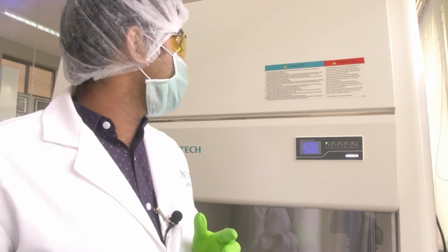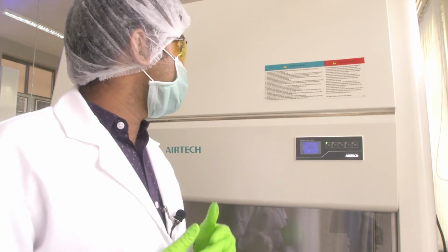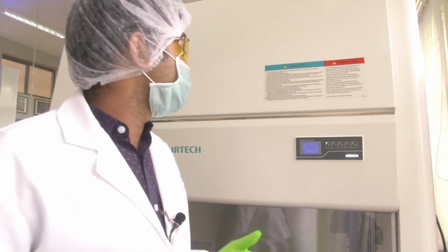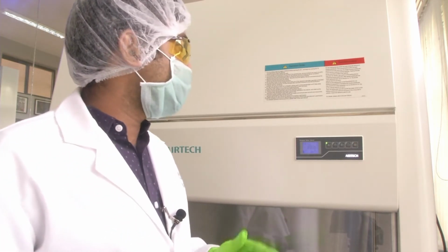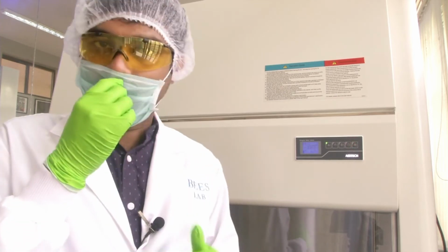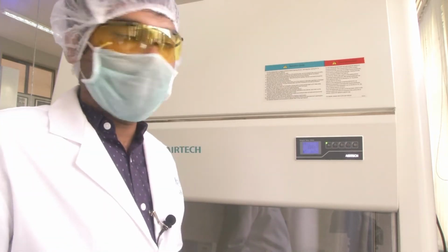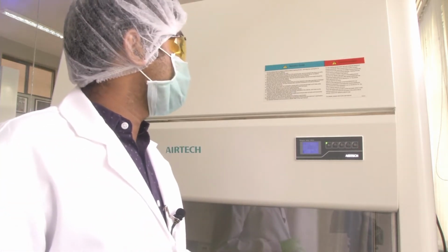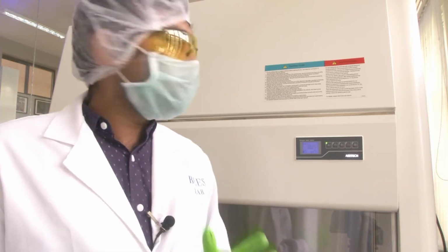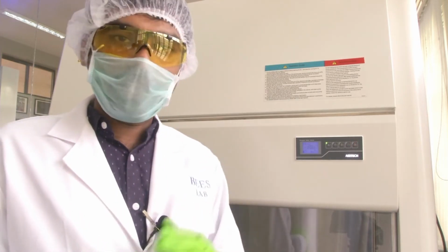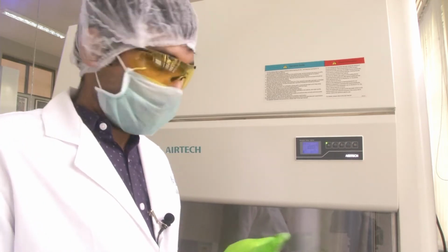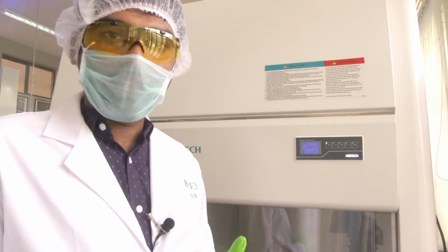Keep away from the UV light when it is on, so as not to cause injury to skin and eyes. Clean the drain, spillage trough and work table frequently. Please, we have to keep this area clean. Please choose neutral detergent and avoid chlorinated cleaners, because they can react with the surfaces inside the biosafety cabinet and cause corrosion.